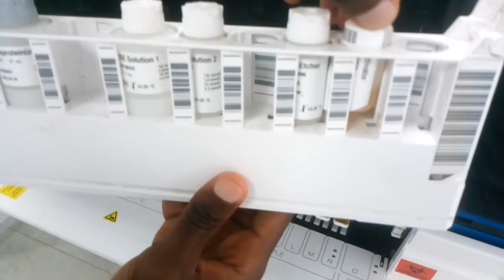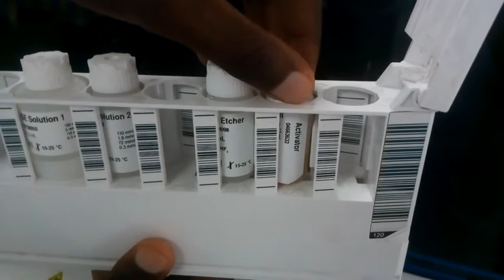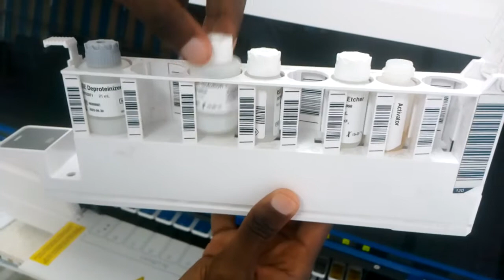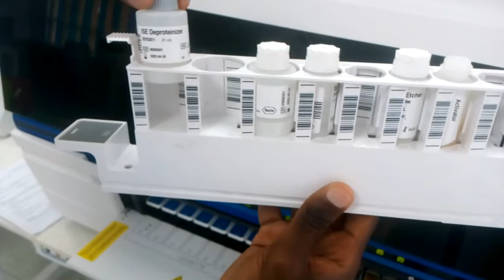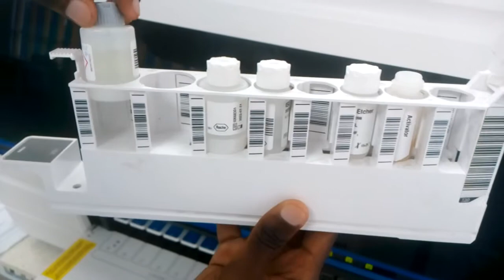Once you finish checking your reagents, the second procedure is checking your activator in the ISE rack. So you go to the ISE rack, then you check that all the reagents that you need in your ISE rack are sufficient, starting with the activator. This is the activator. Ensure the activator is sufficient. This is the etcher. ISE solution 2, ISE solution 1, ISE deproteinizer. So ensure all the fluids, the solutions, the reagents are sufficient before you can start the day.